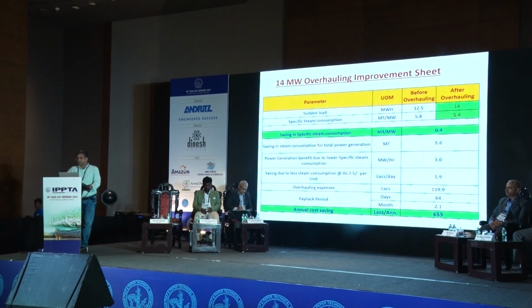In the 14 megawatt turbine overhauling, specific steam consumption was 5.8 metric tons per megawatt before, and after overhauling we achieved 5.4. This 0.4 metric ton per megawatt saving has given us substantial savings of around 6.5 crore per annum.